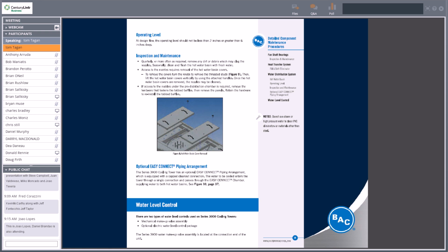If you see ice build up from the bottom up, it means that your controls may be a little bit off, and you're trying to generate too cold of condenser water coming out of the tower. So, easy way to tell. Most fan motors are reversible, so that if you wanted to reverse the direction of your fan motor to kind of blow some ice off your cooling tower, that can be done. It's usually done by reversing the leads in the VFD or in the motor control center.